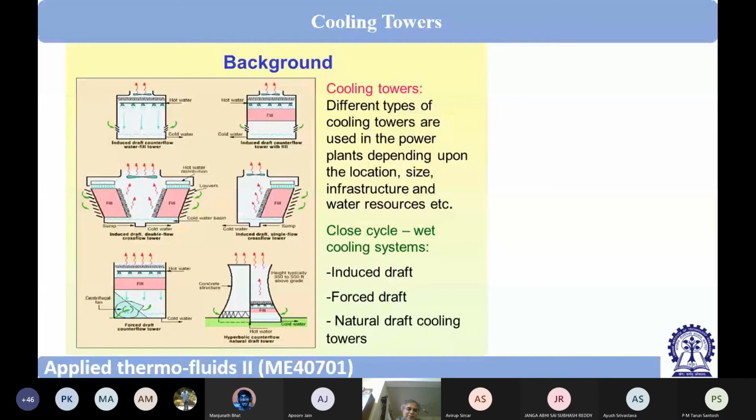About the venturi-like shape, people say many things, but wrongly. Some people say it is due to increasing the velocity. That is not the case at all. This is a very large civil engineering structure, a shell structure, and this shell has to be made thinner for low cost, low weight, etc. If we give some sort of curvature, then the shell will become stable, and we can go for a thinner shell.